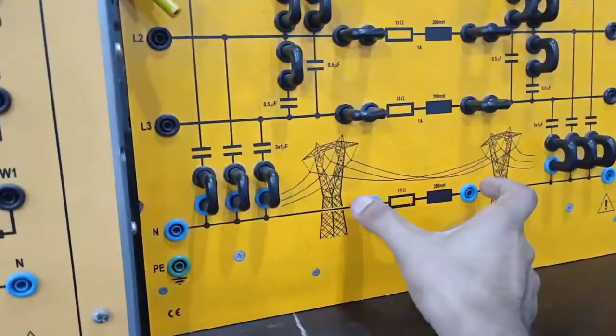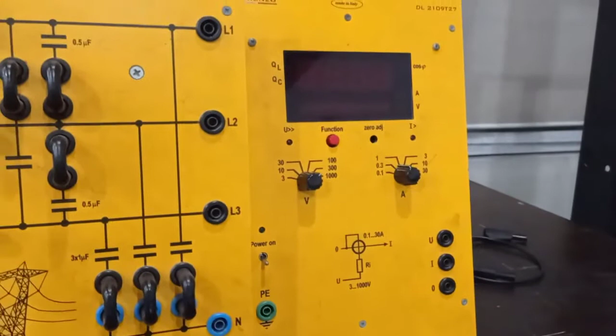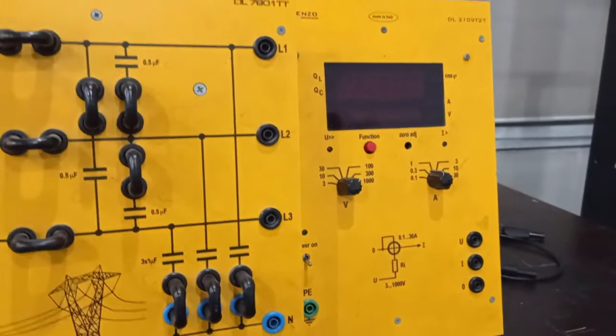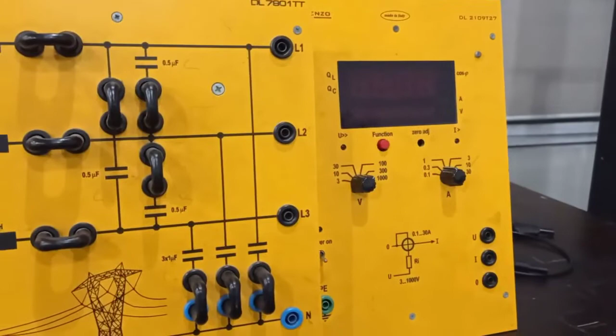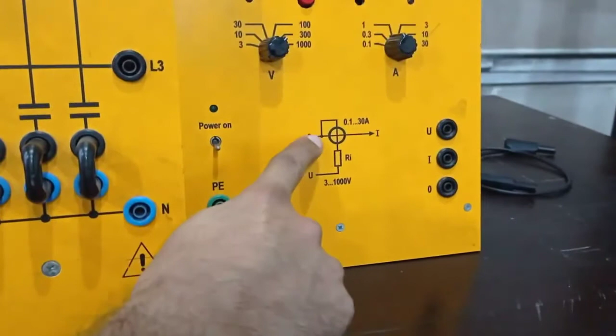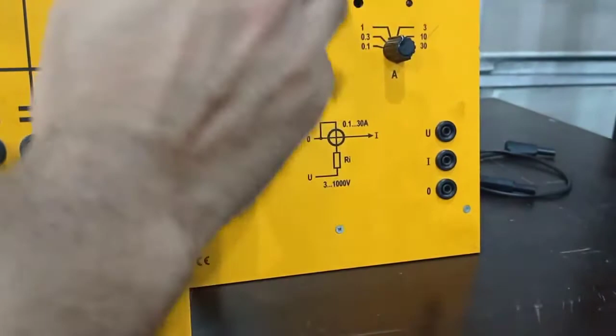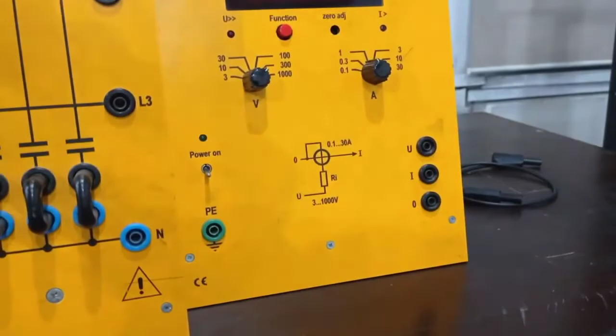Now here short circuit this ground resistance as well. Next is to connect the voltmeter and ammeter on the other side. Here we can see we have a three-phase power meter that can be used as a voltmeter and ammeter as well. Here we can see a digital power meter that can measure voltage and current as well. Take help from the diagram given on this meter to connect the ammeter and voltmeter properly. You will connect this ammeter and voltmeter to determine the fault current as well as the healthy phase voltage during the fault and before the fault.